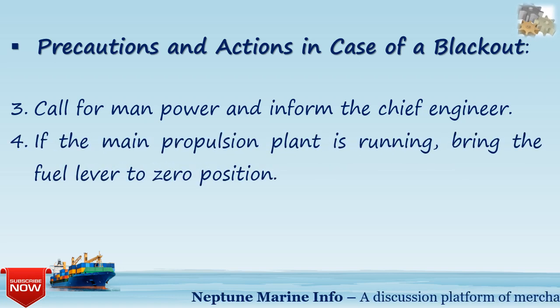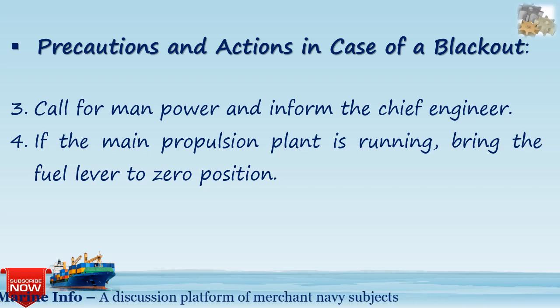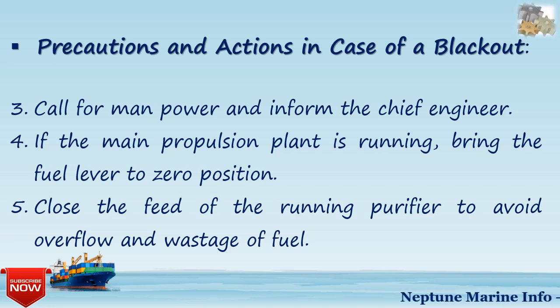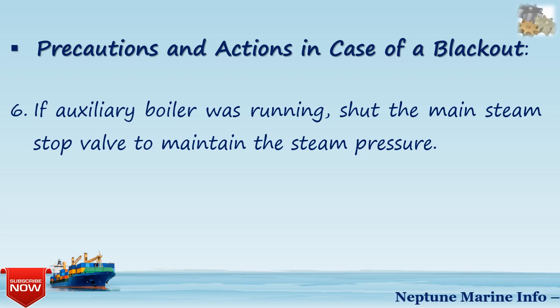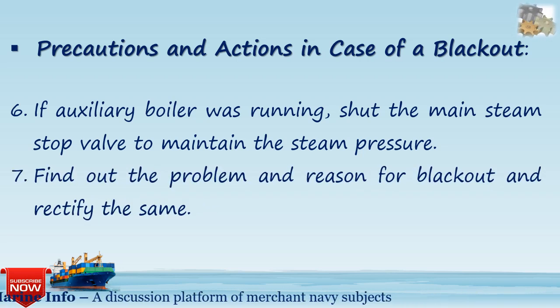Fourth, if the main propulsion plant is running, bring the fuel lever to the zero position. Fifth, close the feed of the running purifier to avoid overflow and wastage of fuel. Sixth, if the auxiliary boiler was running, shut the main steam stop valve to maintain steam pressure. Seventh, find out the problem and reason for the blackout and rectify it.